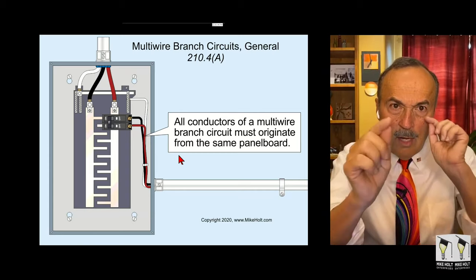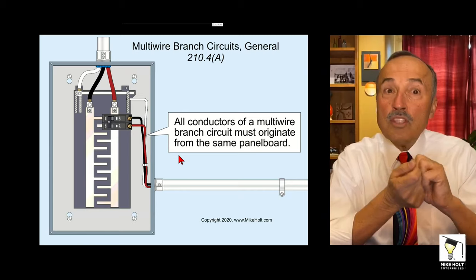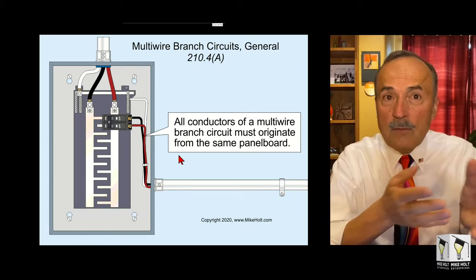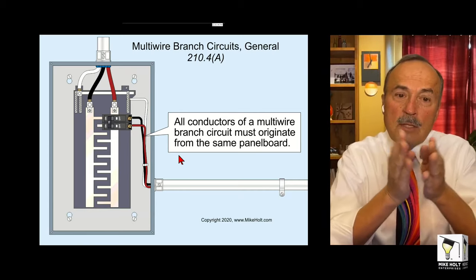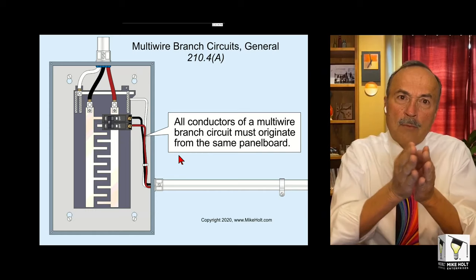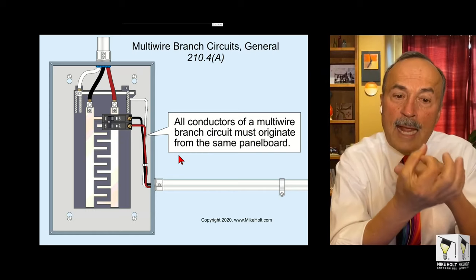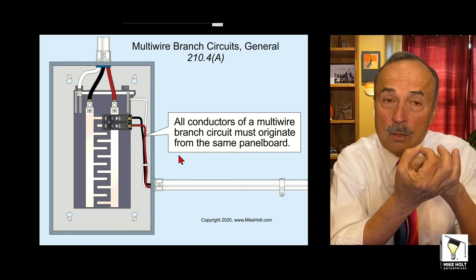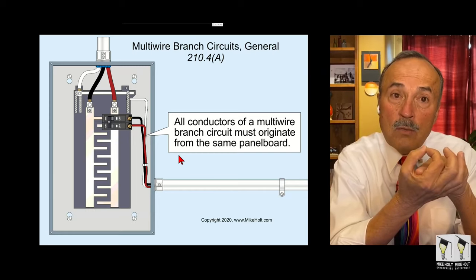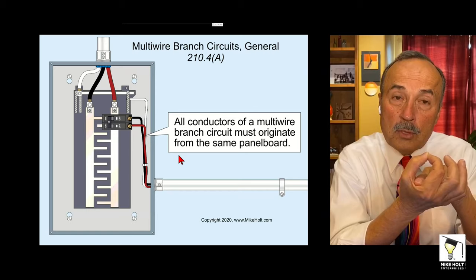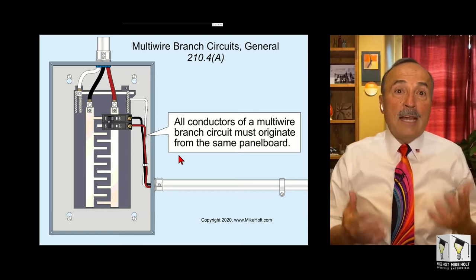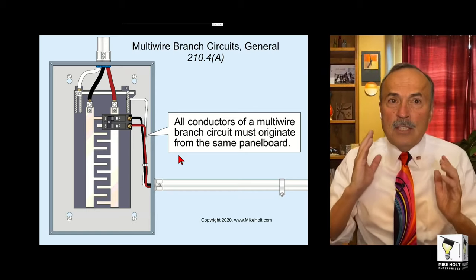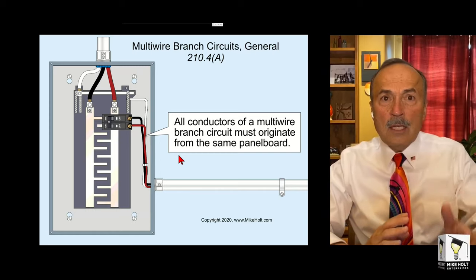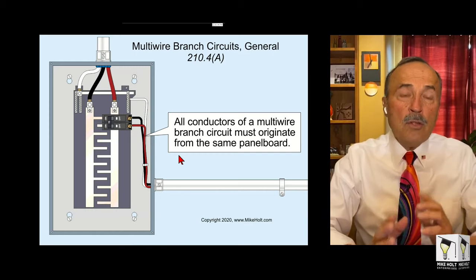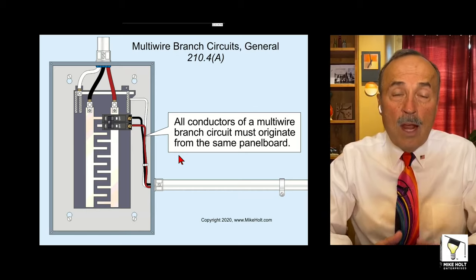See, electrons go out on the two hots, and there's a common neutral, or a shared neutral, or an Edison circuit, whatever you might want to call it. That means that the electrons are going out and returning in their proper path. And if you put an amp meter around two hots and a neutral, properly wired, you will detect what? 0 amps. Perfect. Well, the AFCI and the GFCI are doing the same thing. They're measuring current going out on the phase conductors, measuring the current coming back on the neutral conductors, and if it's properly wired, it'd be fine.